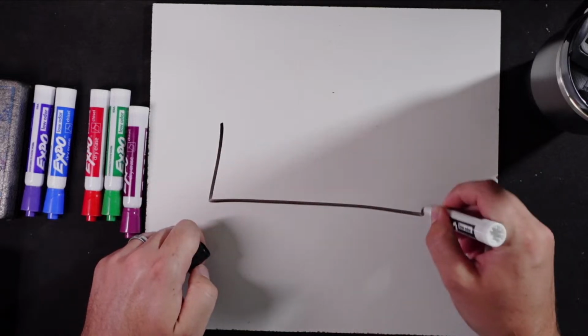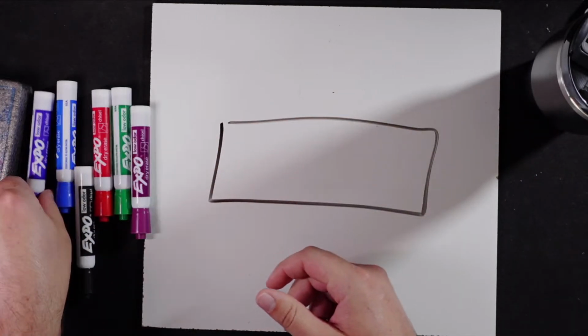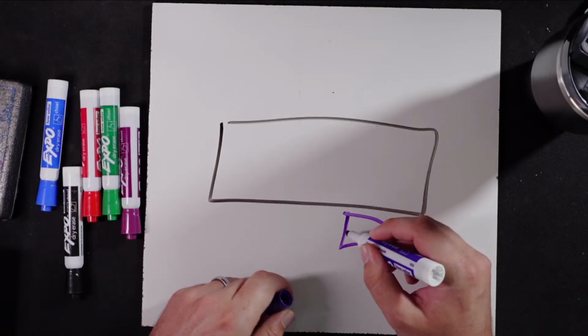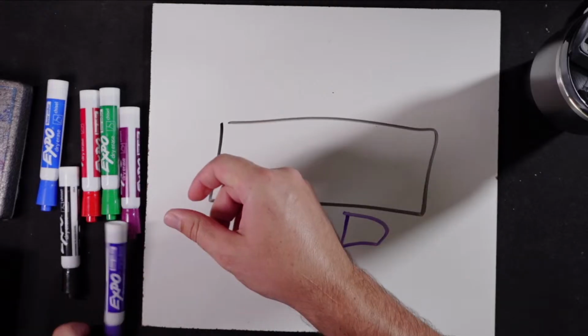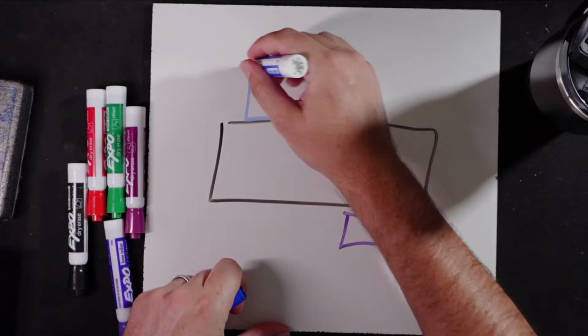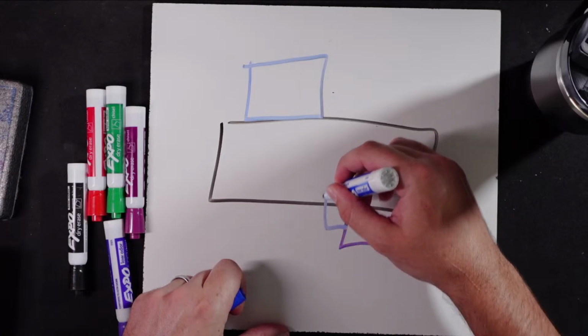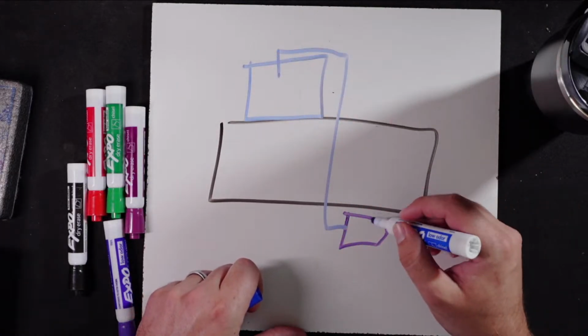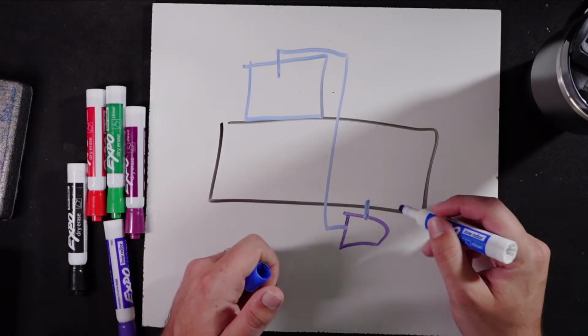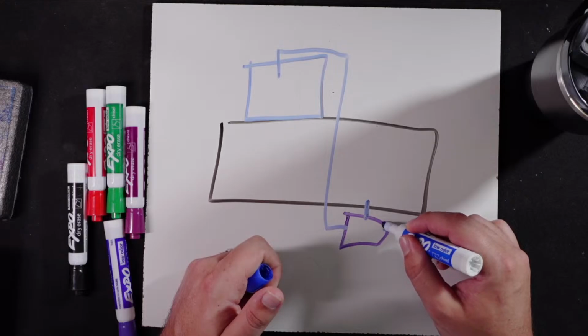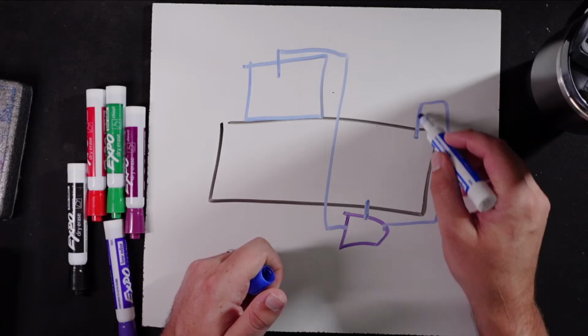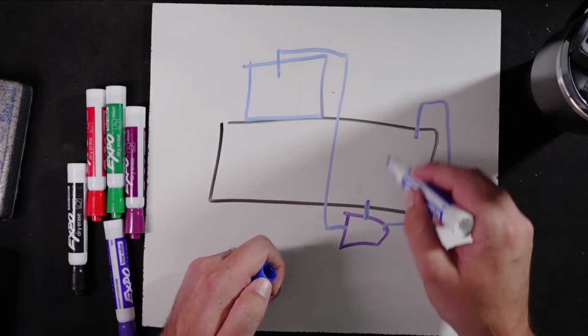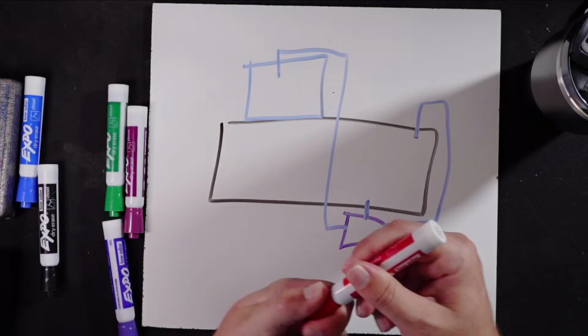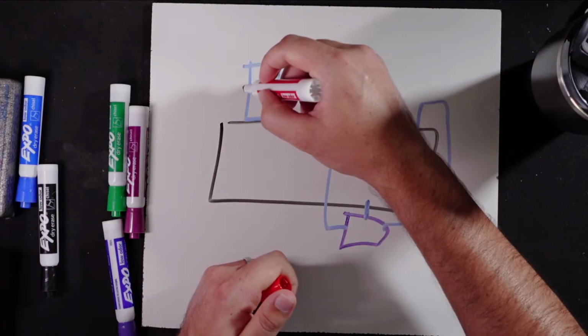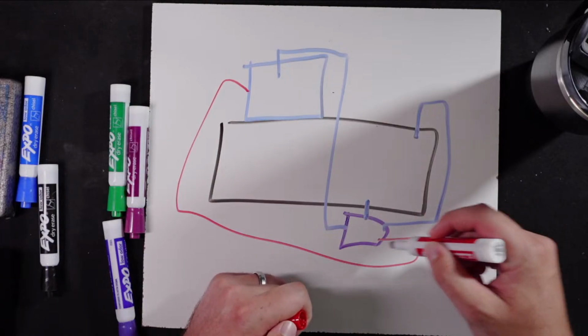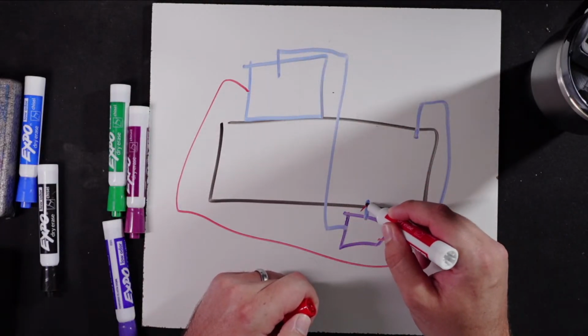This is our evaporator, right? And then we've got our gas pump down here. We've got one line coming up to our compressor up here. Okay, so this is our return line coming up and into the recovery port. We've got our drain line, and depending on your system, let's say you have an older one where we've got, as I learned recently, the newer ones don't have this vent line anymore. Either way, whether you do or don't have the vent line, that's irrelevant. And then we've got our hot gas coming over and pumping in to push all that back out. And right here is your check valve.